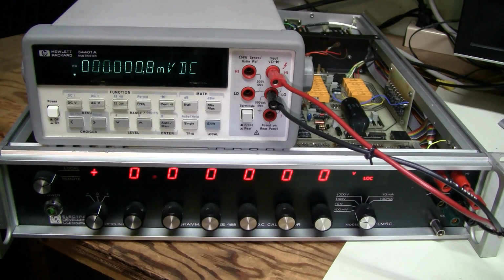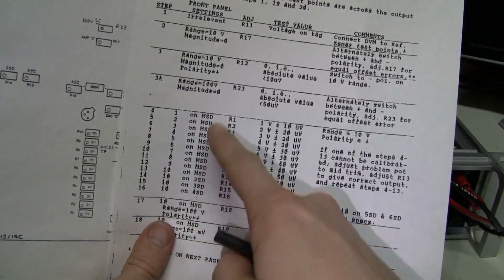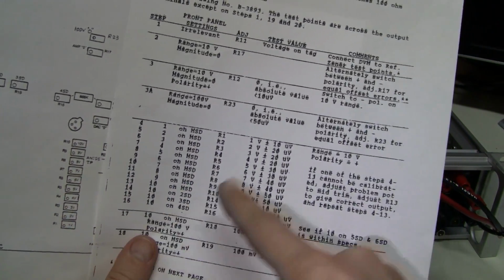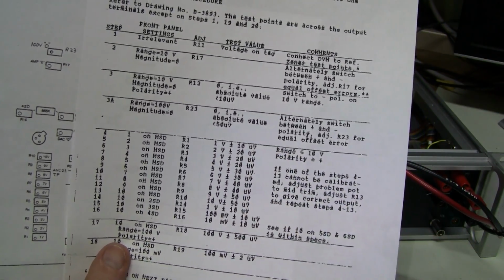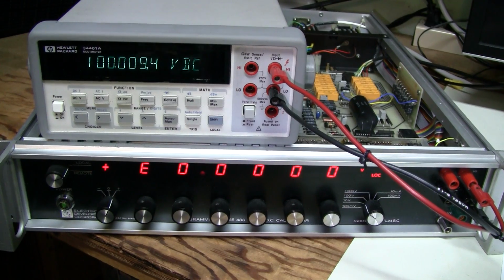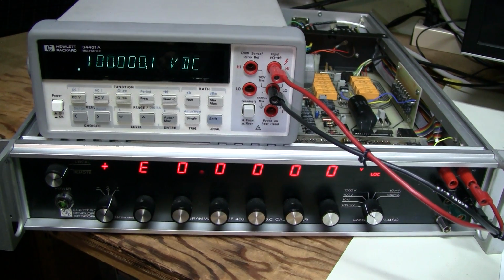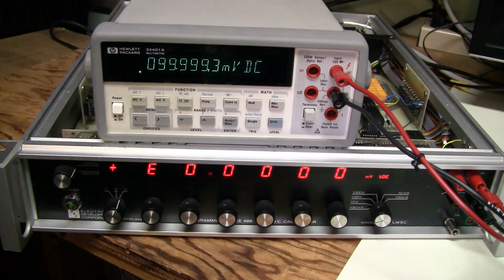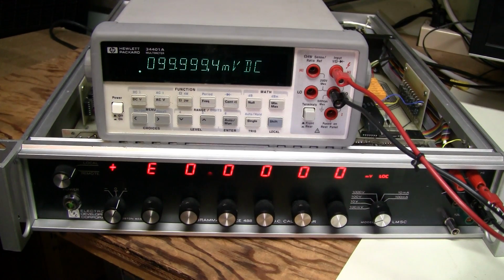The next step would be to adjust the 0 point of the amplifier for the 100 volt range, but as we've seen before, there is no such adjustment in my unit, so I will have to skip this step. And the next big step is to go through all positions of the most significant digit and adjust these trim pots to have this voltage within this tolerance. Alright, the big step is done, and now we need to adjust this 100 volt range full scale to be within 500 microvolts. Alright, this step is done as well. The next step is to adjust full scale on the 100 millivolt range to be within 2 microvolts, and it is already there. So the next step is to adjust the current ranges.